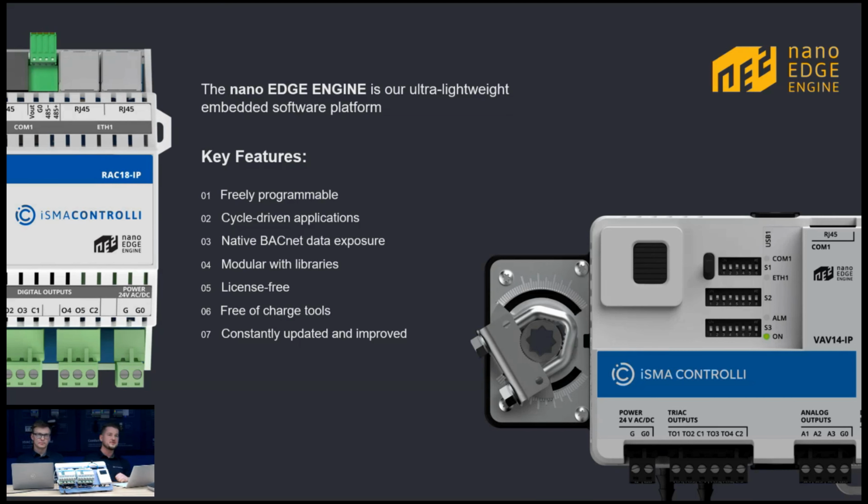Another important feature is the native BACnet data exposure. The controller itself can be discovered using the BACnet network, even out of the box. There is no configuration to do that. The feature number 4, which is modularity with libraries, means you can create applications based on the existing libraries. You can install more libraries to the controller, and in the future, you'll be able to build your own libraries using the C# programming language.